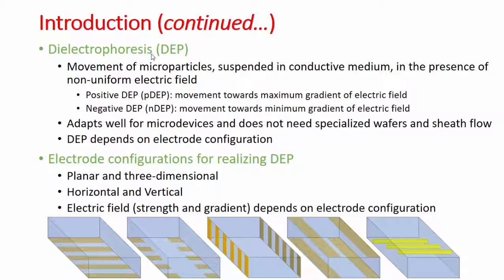The reason we adopted dielectrophoresis for a separation device is because DEP scales well with miniaturization. Because the electrodes are really close to each other, the electric field developed is inversely proportional to the distance. Since the device is really small, the distance between the electrodes can be very small, meaning you only need a very small voltage to generate a very high electric field.